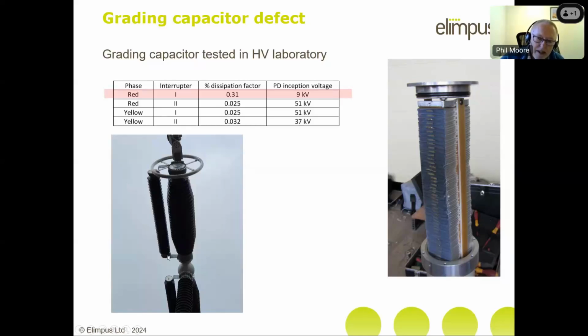And if you were to take one of those apart and actually take the porcelain off it, you'd end up with something that looks like this photograph on the right hand side. Now, to be perfectly clear with you, that is not the grading capacitor that came off this circuit breaker. That is actually one out of a GIS. And in GIS grading capacitors, they normally use SF6 gas to insulate it, whereas in an AIS there's usually oil. So when you take these apart, you have to let all the oil out.